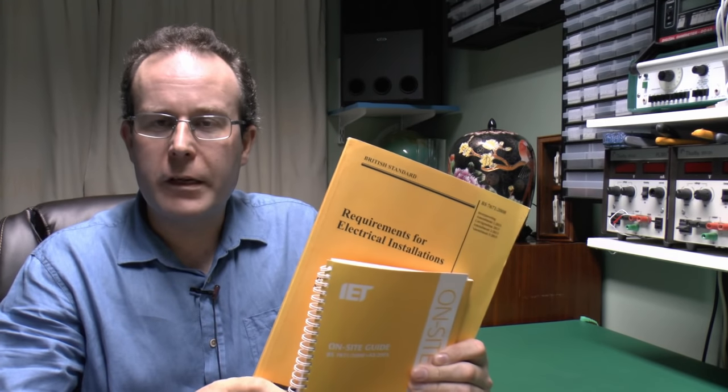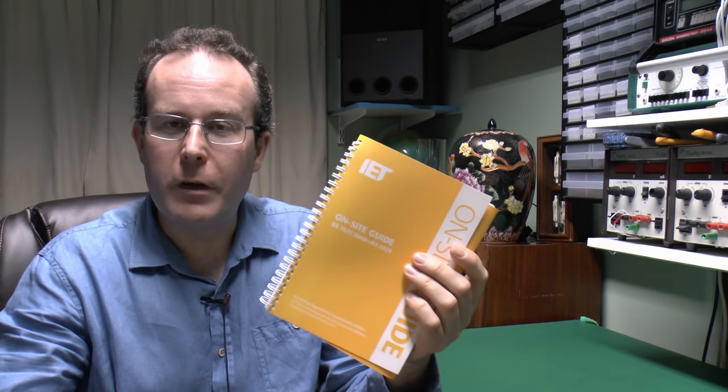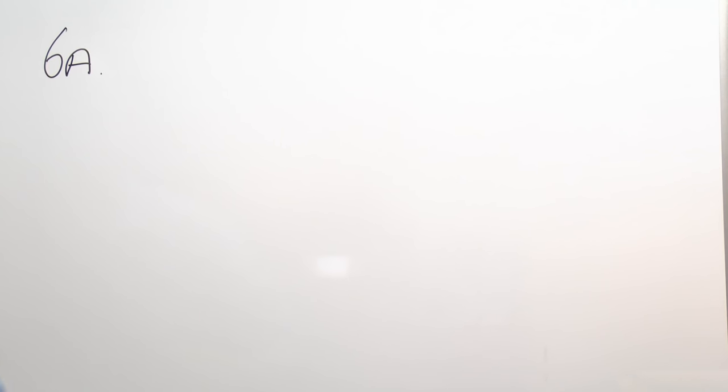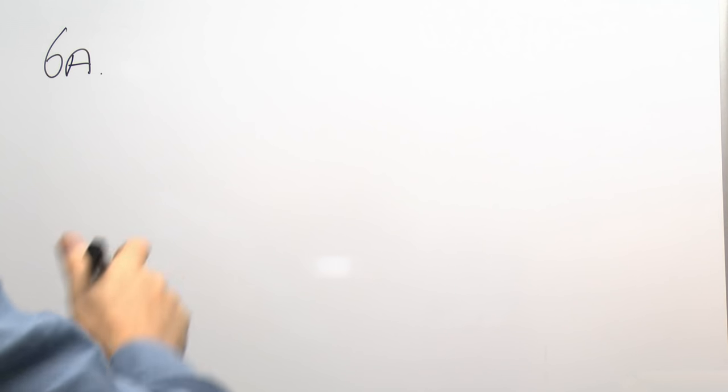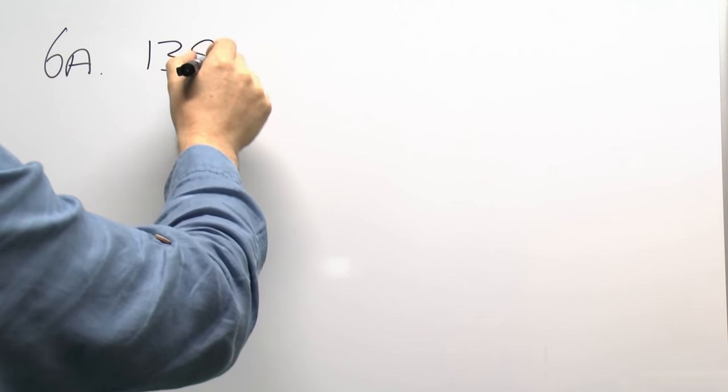That's what the books say — not very helpful: BS 7671 gives nothing, and the on-site guide gives somewhat outdated guidance. So let's look at some practical examples. For lighting in a typical house, a single lighting circuit would be a 6 amp circuit at 230 volts, equating to a power of 1,380 watts — which is actually quite a lot.